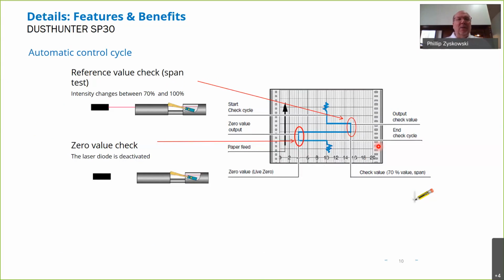What's a little bit different is the way that we do our control cycle. It's a way to measure the integrity or really determine the integrity of the measurement. And so you've got your light beam from the laser. Typically, it's crossing this plane here. And what we do is step the intensity of our laser from 70% to 100%. So when we do that, you can see on this chart recorder the step changes that you would expect. We turn the laser off in the next step, and that becomes our 0 point. And you can see here how that would be indicated on a chart.